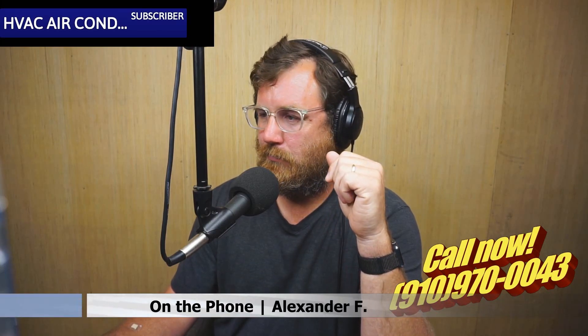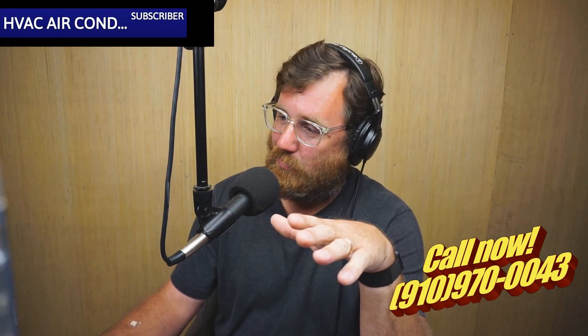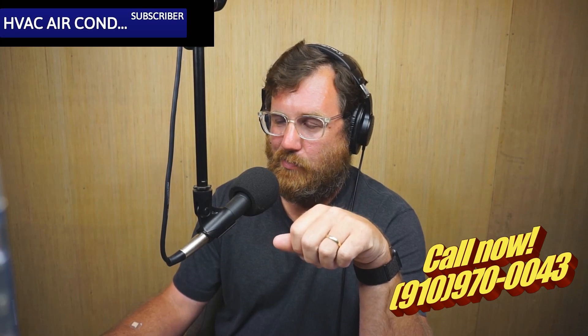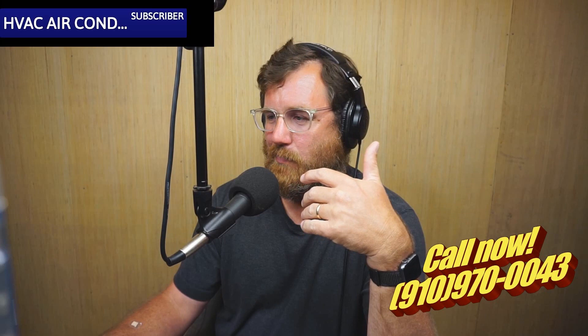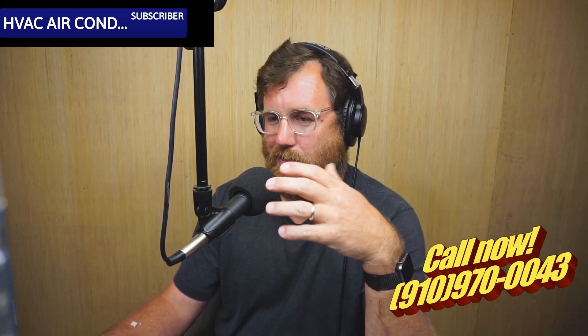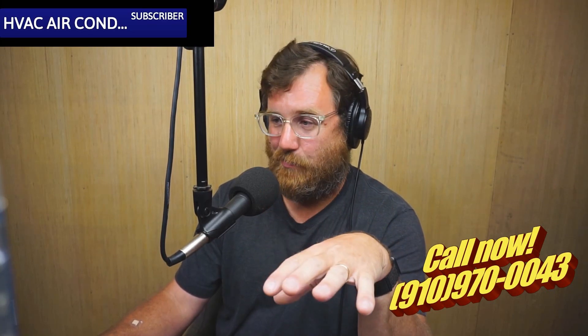How did your ordeal with the R22 replacement go? I just did that today actually. I went in there and the vacuum was being a son of a gun — this unit must have been rode hard and put up wet, literally, because it took a long time to evacuate it down to what was reasonable.